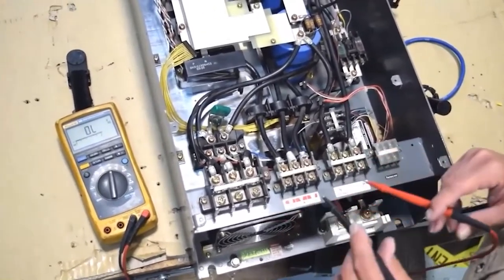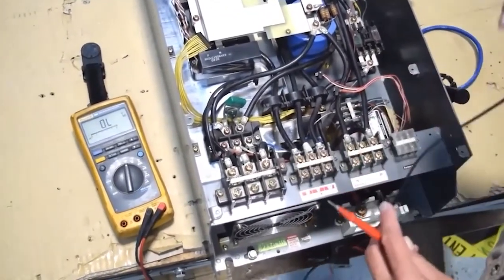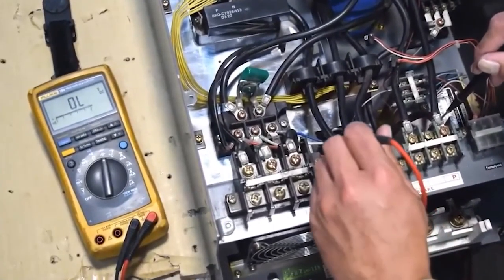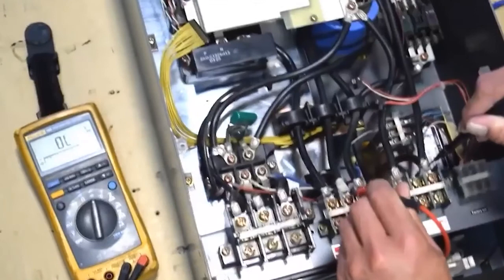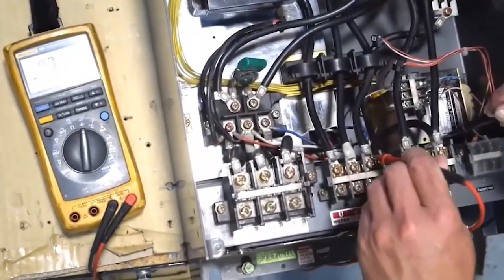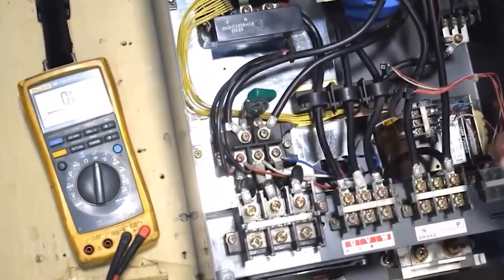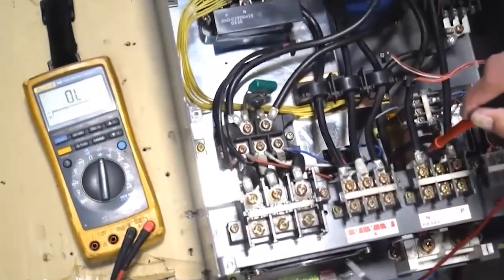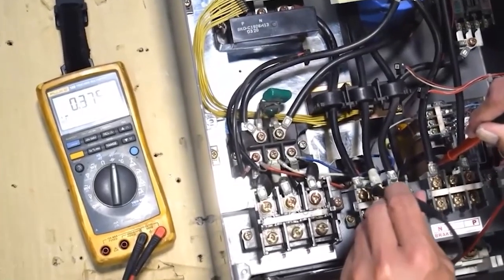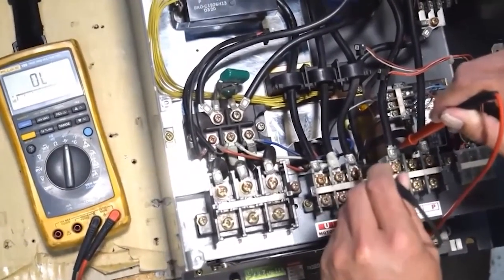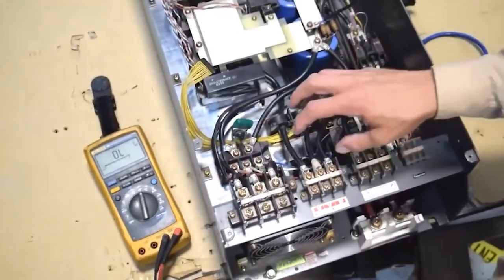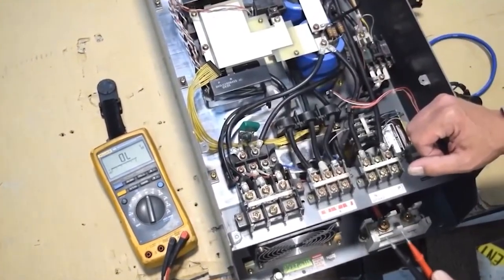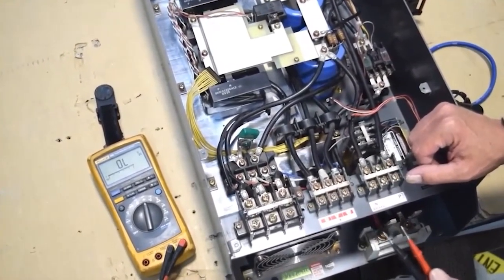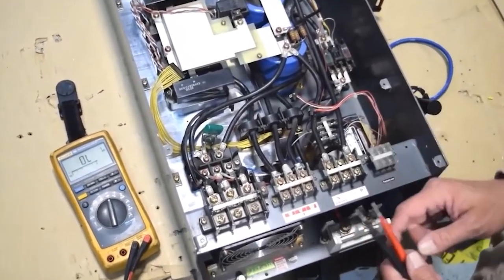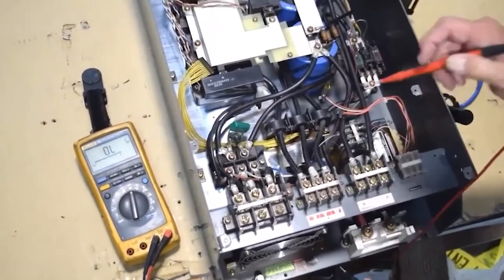All right, so now I'm going to switch my leads around, and then I'm going to measure my outgoing. So once again, negative lead, positive bus. I'm going to measure all my output. Once again, it's normal for those to measure a little bit less than your incoming, but they're all consistent with each other. So I'm getting about 375 all the way across, and that's normal. Now, if I get anything that's an open or a short, that's an indicator that the diodes and the transistors have an issue. Or if I get too much of a variance between the transistors or between the diodes.